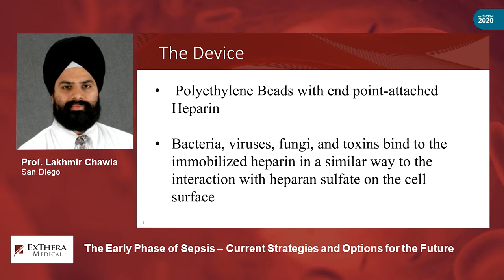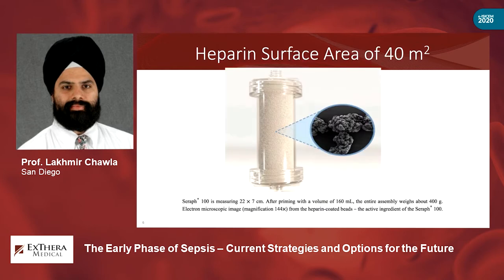Most of us think of heparin as what we dose patients with to achieve anticoagulation. But heparin has a large series of other properties. You can think of the device as a very large hemoperfusion system that exposes blood to a very large surface area of heparin — about 40 meters squared. A similar-sized dialysis filter would offer only about 2 meters squared of surface area. It's really an enormous amount of heparin surface being provided.